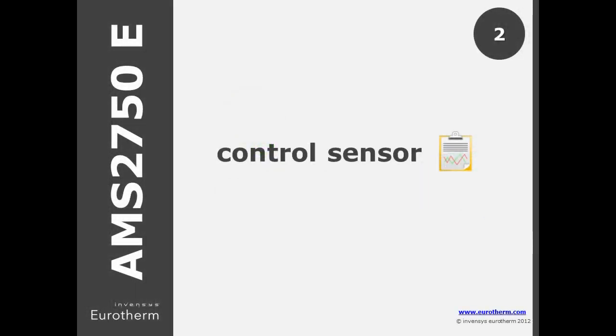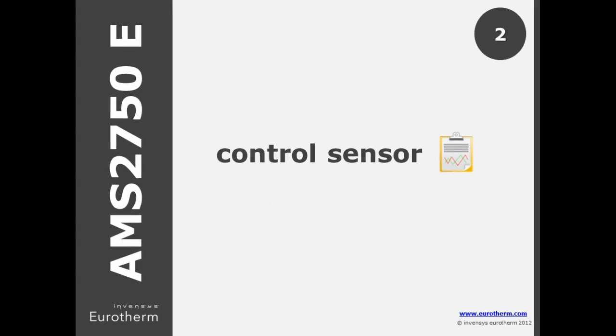In D, the individual control sensor needed to be recorded by the recording instrument. There is a second option in E to use an additional sensor in the same sheath as the control sensor, no more than 0.38 inches apart, and this second sensor is linked direct to the chart recorder.